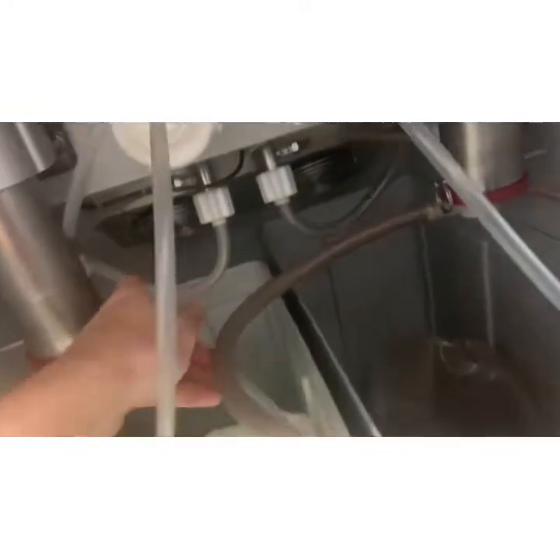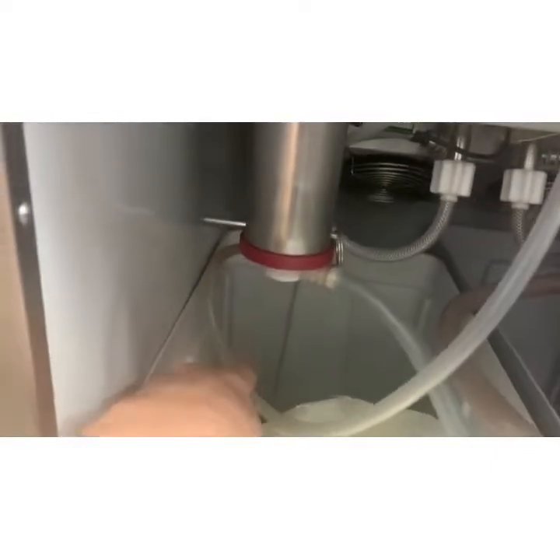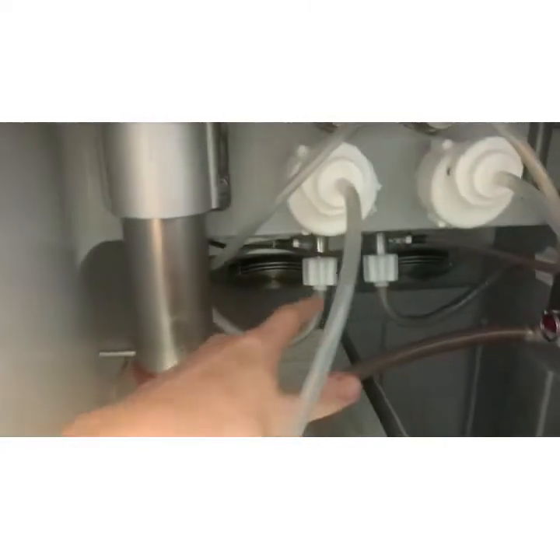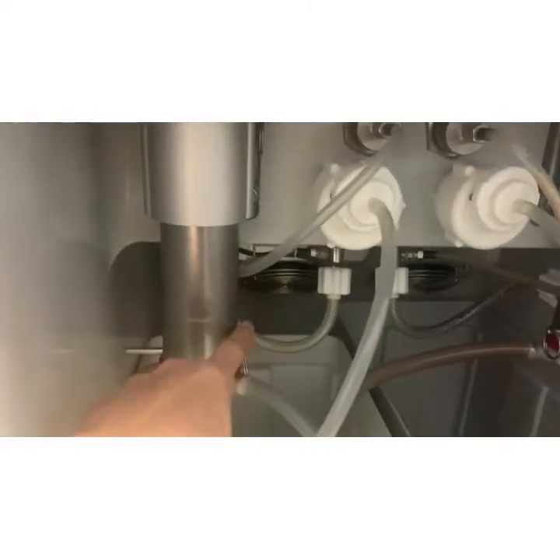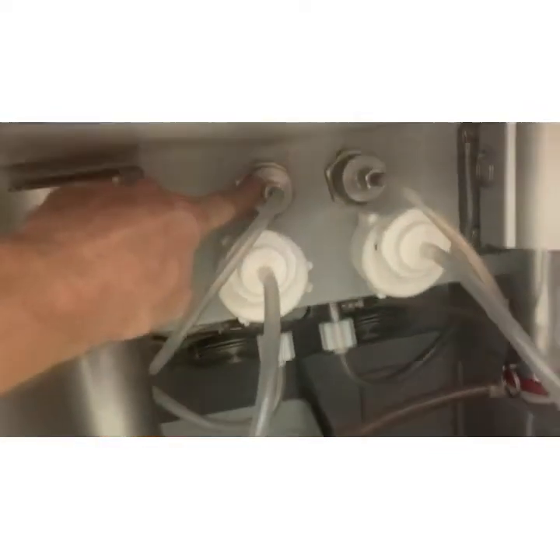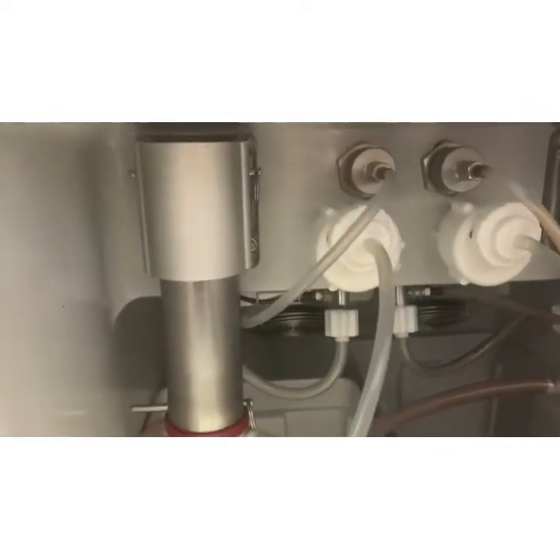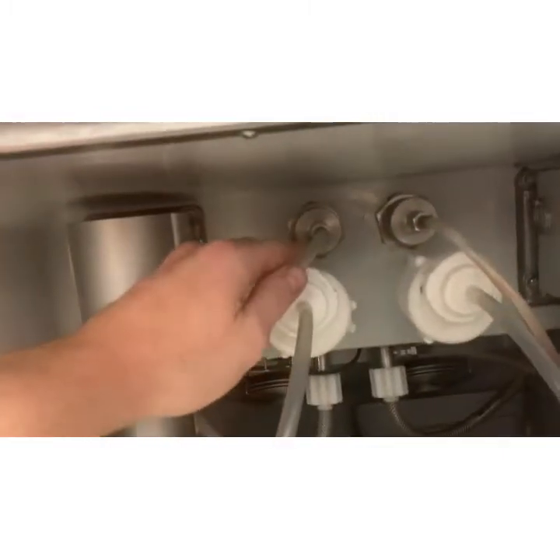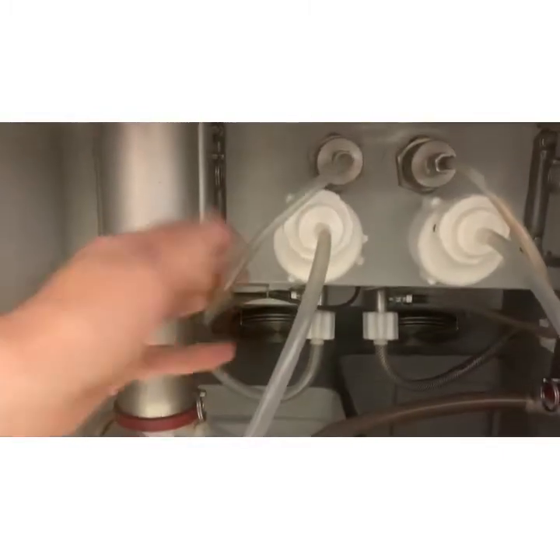The machine into the barrel of the machine here. There's actually a pressure sensor that stops the pump when the barrel's full. When it's trying to pump, the pressure gets too high, it pushes a bladder inside of these devices which I'll show you and it stops the pump. Normally when the pump won't run like this, it's because the bladder is sensing that it's full even though it's not.